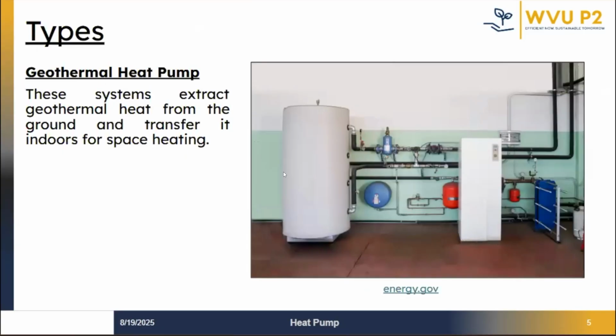Next, we have geothermal heat pumps, which are also known as ground source heat pumps. These systems extract heat from the ground, which maintains a relatively constant temperature year-round, usually between 45 degrees Fahrenheit and 75 degrees Fahrenheit, depending upon the location. Ground source heat pumps circulate water or refrigerant through underground pipes, either in a horizontal or a vertical loop. This allows them to deliver consistent performance regardless of outdoor air conditions. Because the ground temperature is more stable than air, ground source heat pumps tend to have a higher coefficient of performance, often ranging from 3.5 to 5. This makes them one of the most efficient HVAC systems available. While the initial installation cost may be high due to the excavation and drilling that needs to be done, the long-term energy savings and low maintenance requirements can result in lower life cycle costs for geothermal heat pumps. These systems are ideal for new buildings, schools, or facilities with available land area or access to borehole fields.